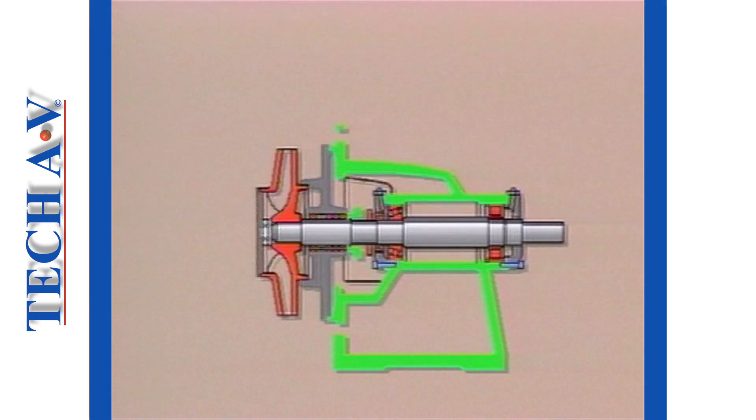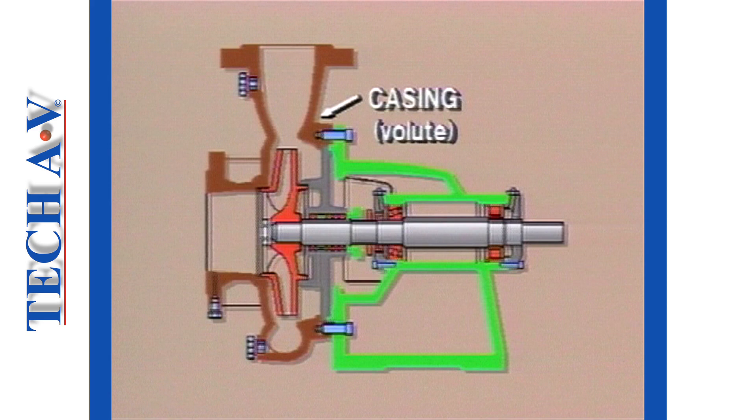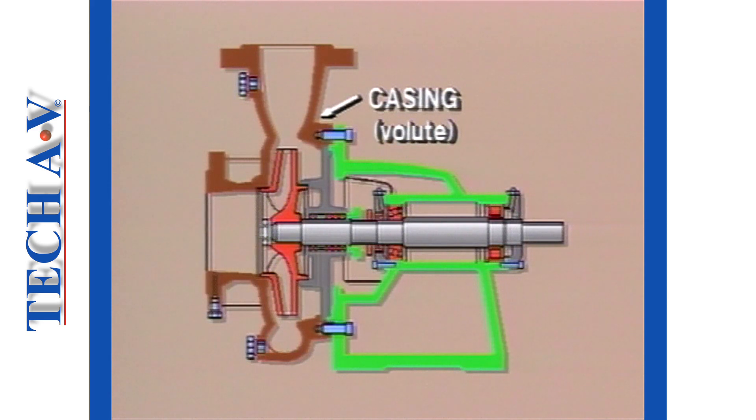Behind the impeller is a cover plate called the gland cover, which is there to provide a water-tight seal. The impeller is surrounded or encased by the casing. On this particular pump, it is known as a volute casing because of its particular design.